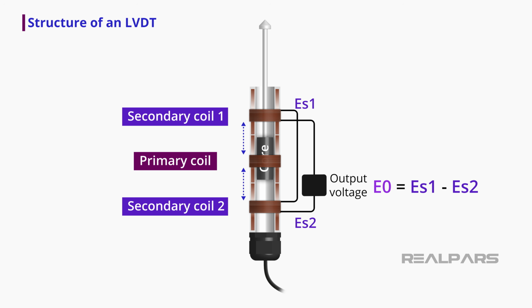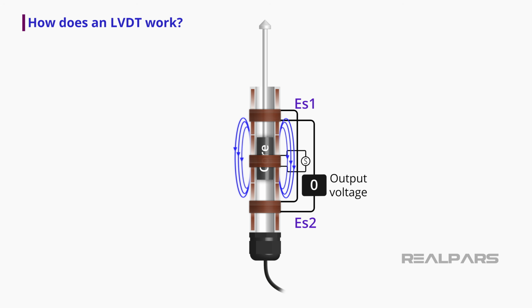On this cutaway, we can also see a cylindrical-shaped soft iron core that is ferromagnetic, meaning that it is highly susceptible to magnetization. This core is attached to a push rod that slides along the tube. This rod is attached to the body to measure its position displacement. Continuous alternating current is applied to the primary coil, generating what we call primary excitation and a varying magnetic field. This primary excitation interacts with the secondary coils, which then induces current and voltage to be produced in the secondary coils. When the ferrous core is dead-centered, which is also called the null position, the induced magnetic flux to each of the secondary coils is equal.